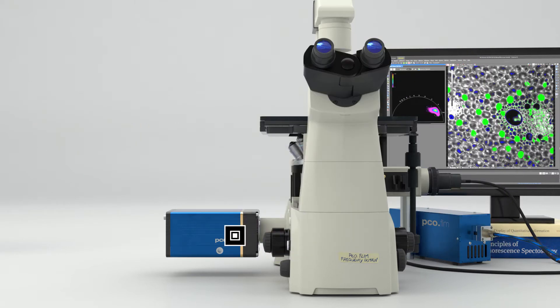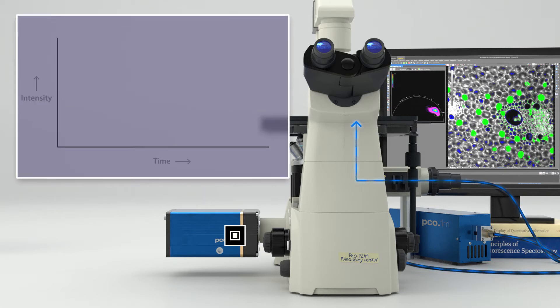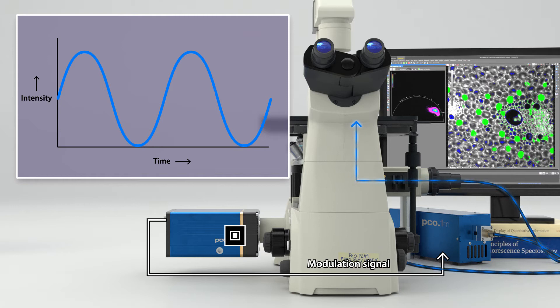In this frequency domain approach, the intensity of the excitation light is continuously modulated using sine or square waves. The modulation source is the camera, which provides modulation frequencies ranging from 5 kHz up to 40 MHz, as well as the signal for dark gating.